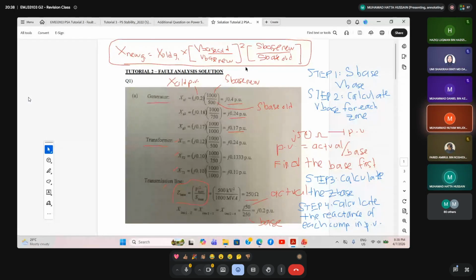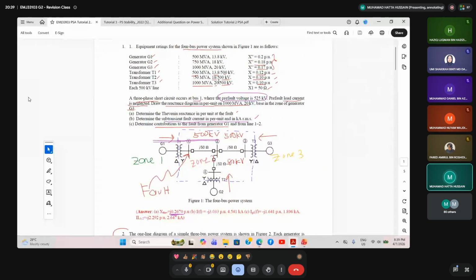Okay, and then for xg1 equal to xg old, J0.2, times S base new divided by S base old. One thing that you need to remember, the S base old is actually from this rating here, S base old 500 MVA.